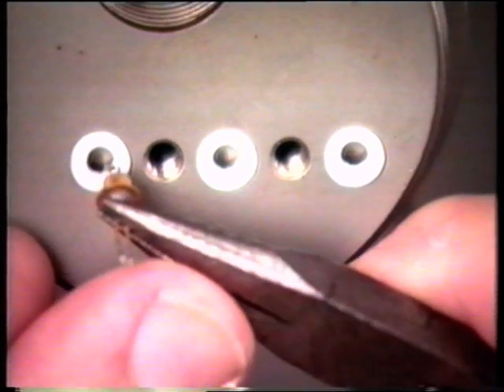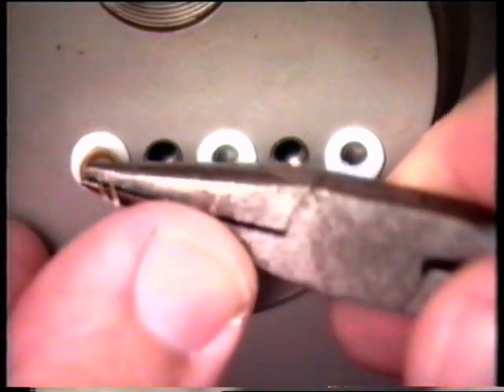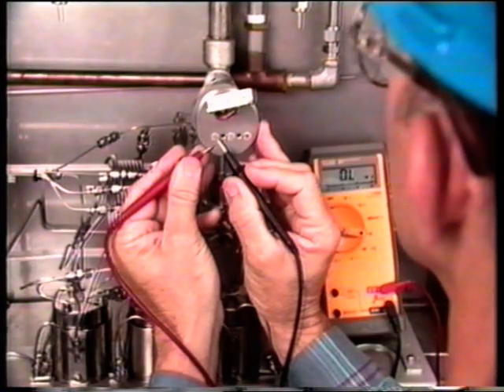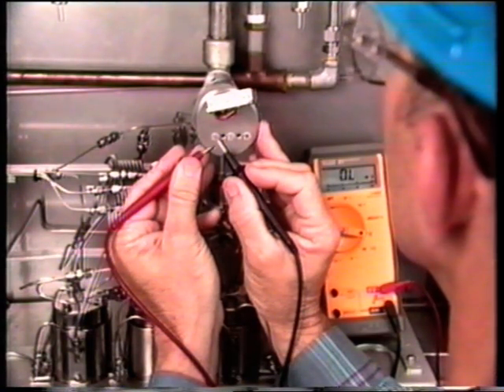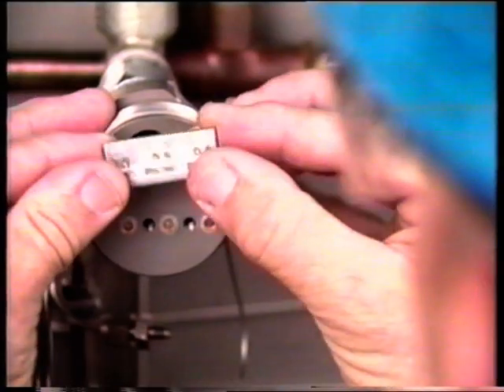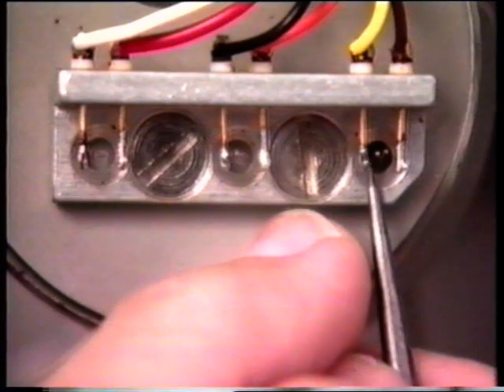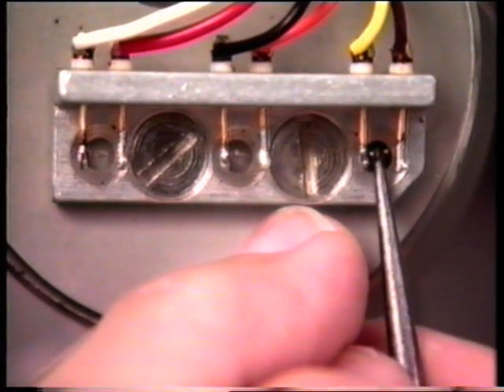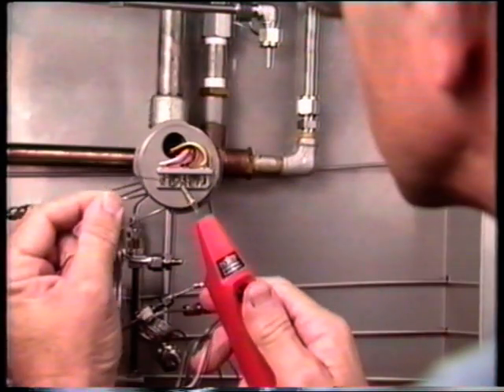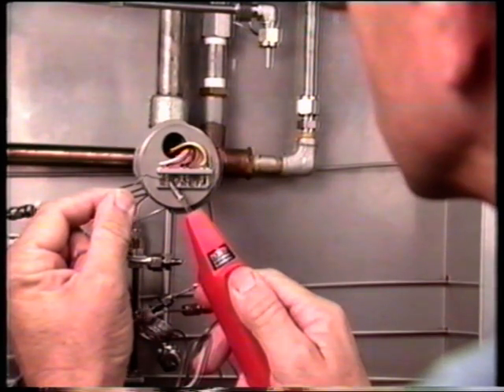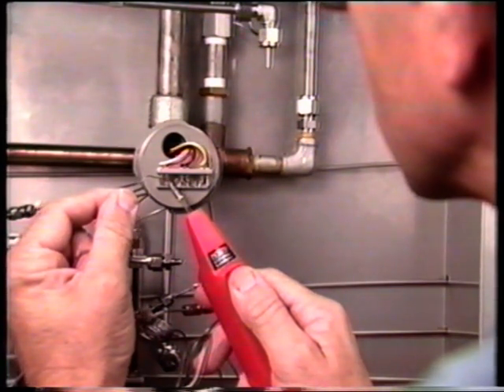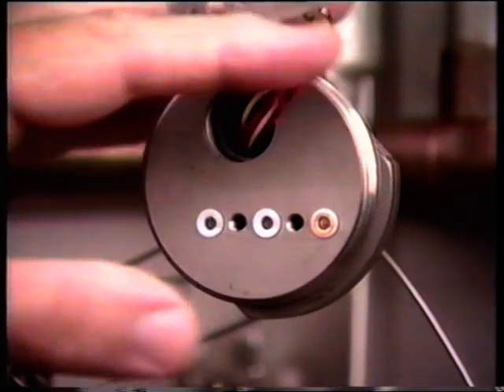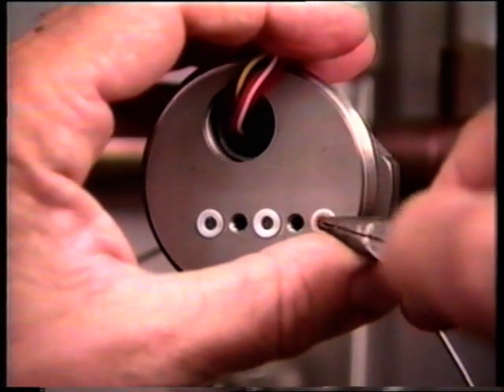Install new thermistors in their proper cavities and be certain to align the thermistor leads. With a multimeter, check the thermistor leads to be certain they are not shorted to ground. Reinstall the retainer plate. Position the thermistor leads so that they contact the corresponding feed-throughs. Use high-temperature solder to solder each thermistor lead to its feed-through. In some cases, thermistor block cleaning and repair may be necessary.